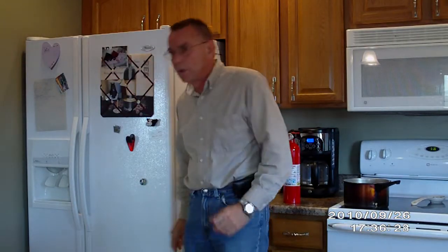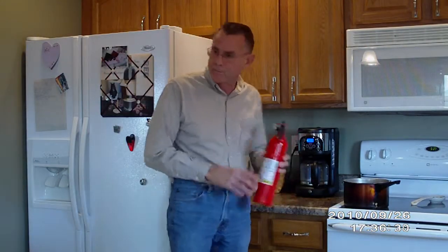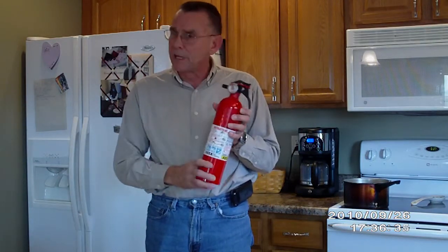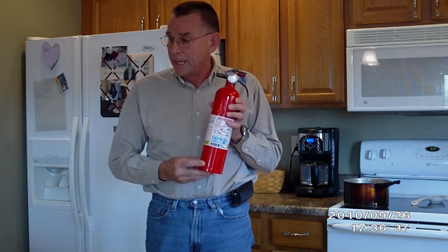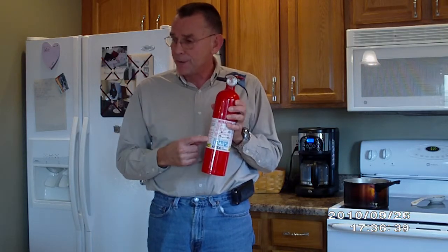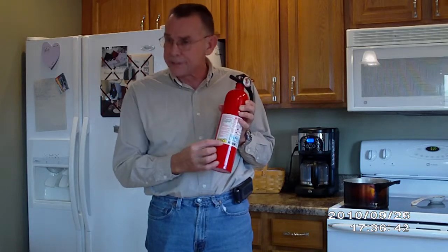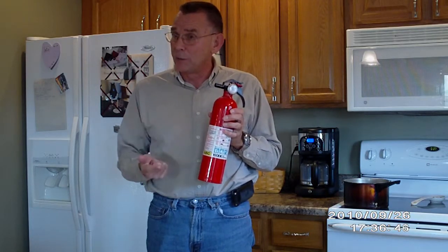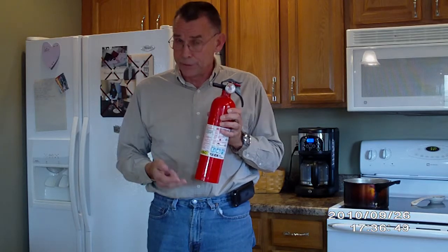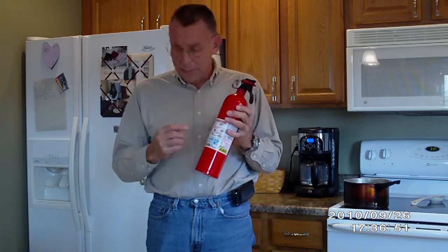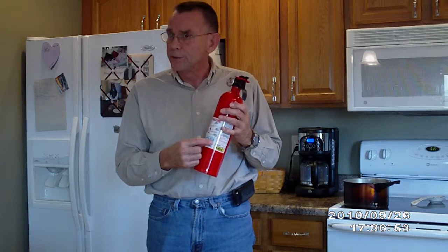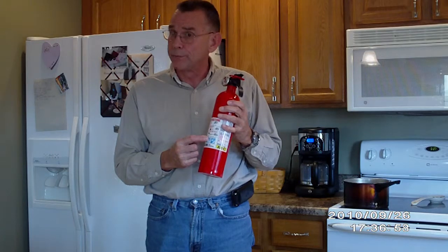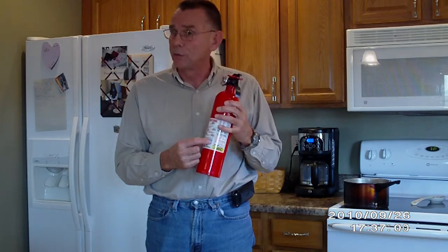So next we want to talk a little bit about the fire extinguisher itself. This is a dry chemical fire extinguisher. There are many types of them out there, but I'm just going to talk about this one tonight. Basically, this is an ABC fire extinguisher. Clearly on the label it says ABC. This could be used on ordinary combustibles, flammable liquids, and electrical fires. So it is clearly labeled. And also in addition, there are pictograms which indicate what type of materials it can be used on. There's a picture of a trash can, a picture of oil or gas burning, and a picture of an electrical cord.